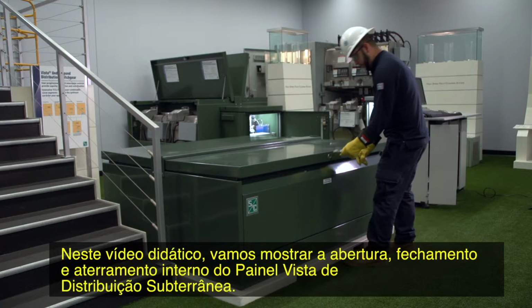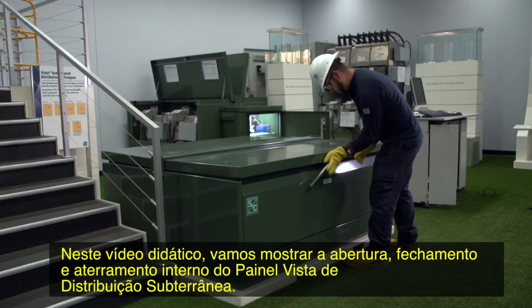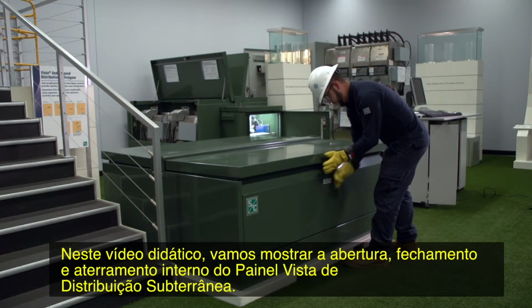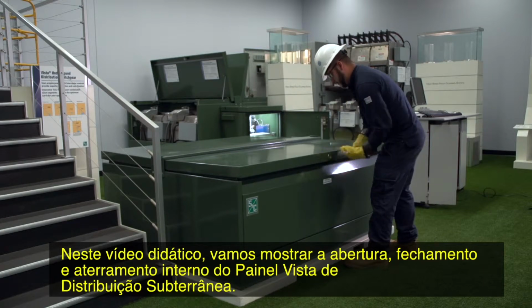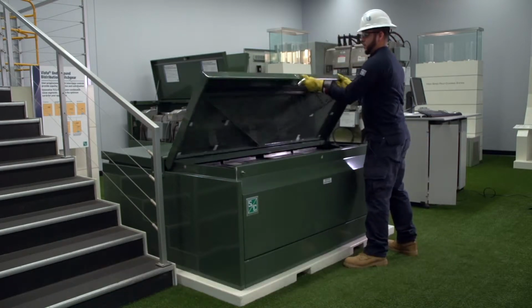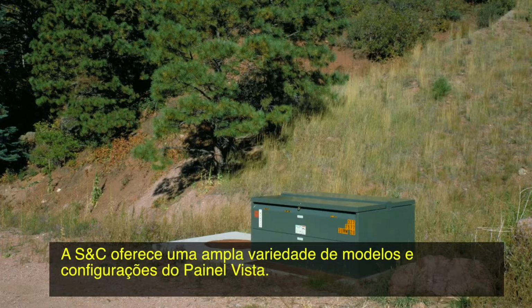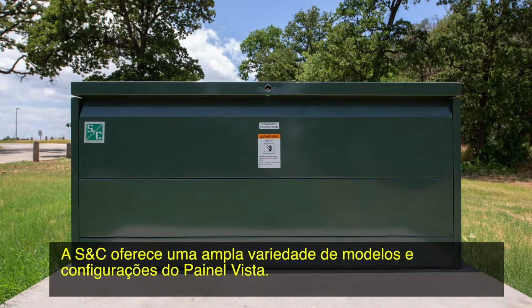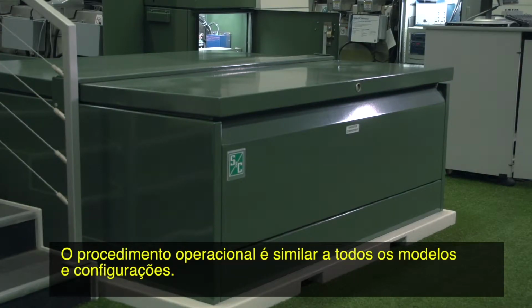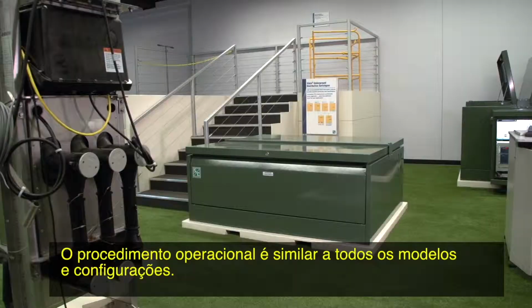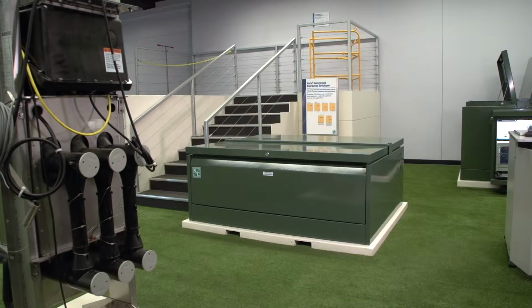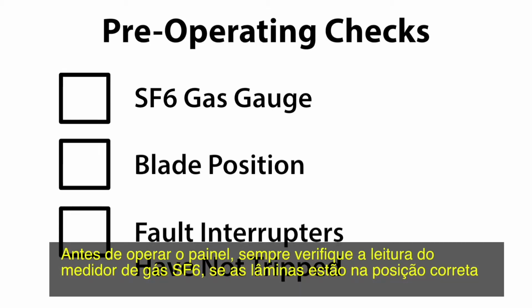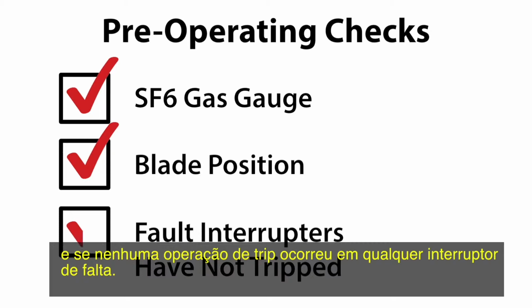In this instructional video, we will perform the opening, closing, and internal grounding of the Vista underground distribution switchgear. S&C offers a wide variety of Vista models and configurations. The operating procedure is similar for all models and configurations. Before operating, always check the SF6 gas gauge, that the blades are in the correct position, and that any fault interrupter has not experienced a trip operation.